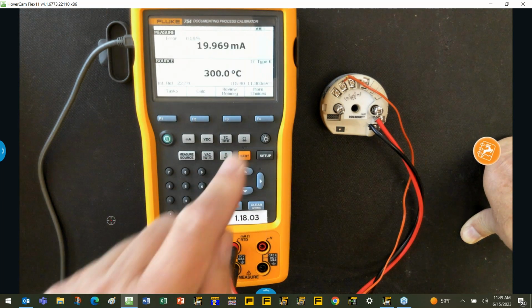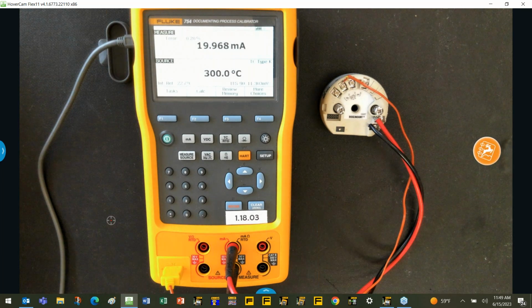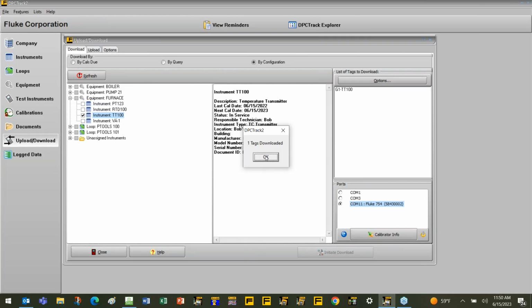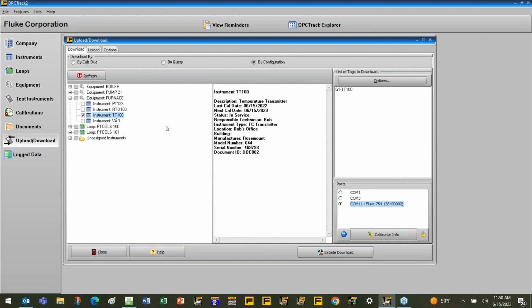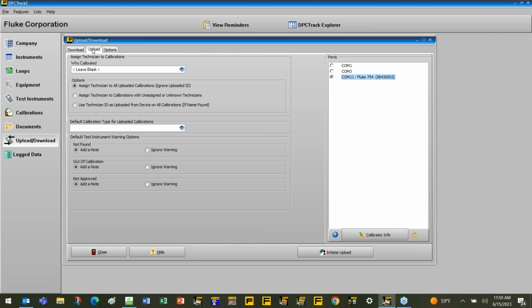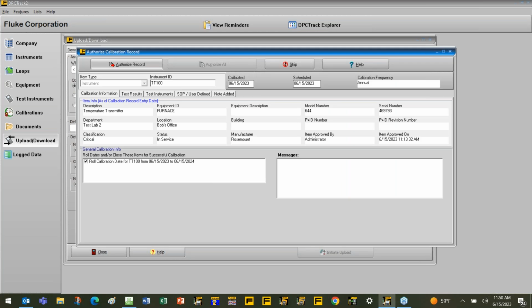Okay. So at this point, we're going to switch back over to the software. And this was that download which was completed. So now we've finished the calibration. We're going to switch to the upload screen. Okay, we've got the 754 still connected here, so we're going to initiate upload. And so now it's going to take that calibration result that was recorded in the 754, and it's going to upload it. Now it's captured it.